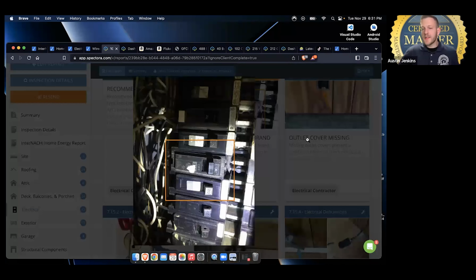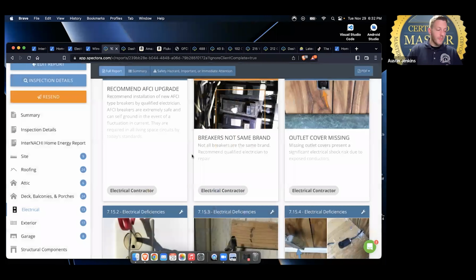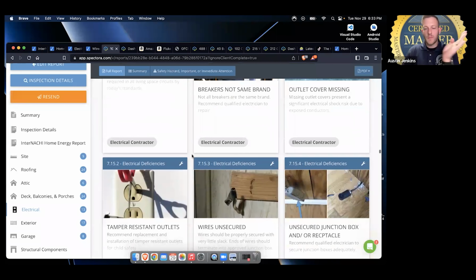The breakers were not the same brand, which is something I like to write up all the time. I get that breakers can be retrofitted between one panel and the next, but they're not designed to be. Square D breakers should be going into a Square D panel, GE breakers into a GE breaker panel.